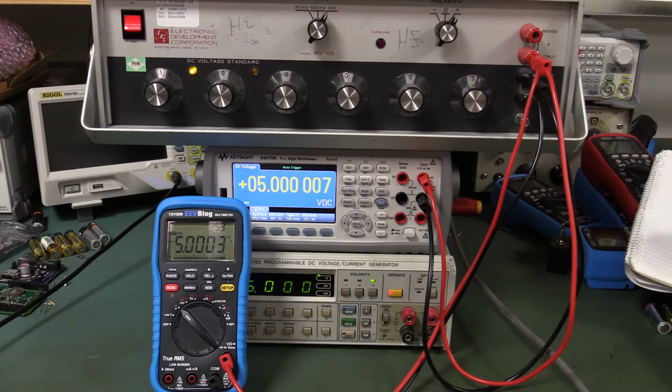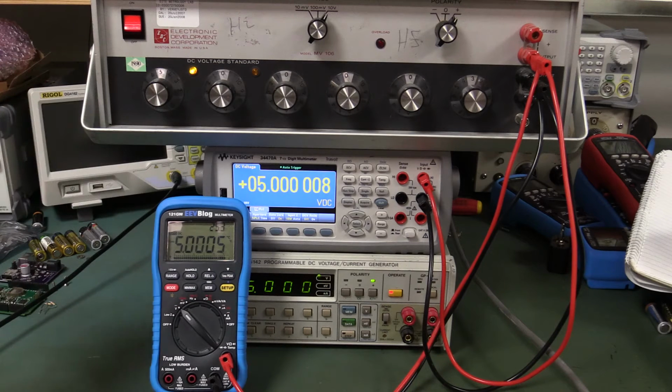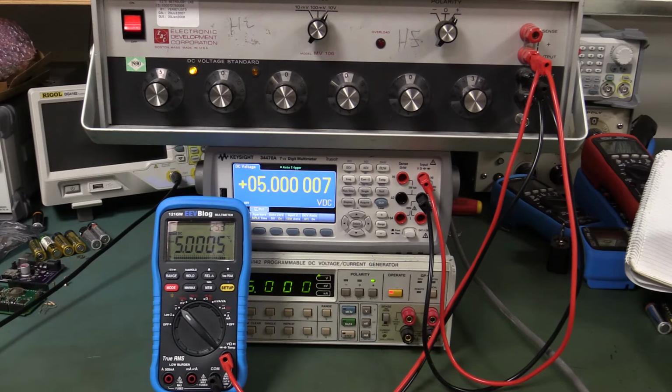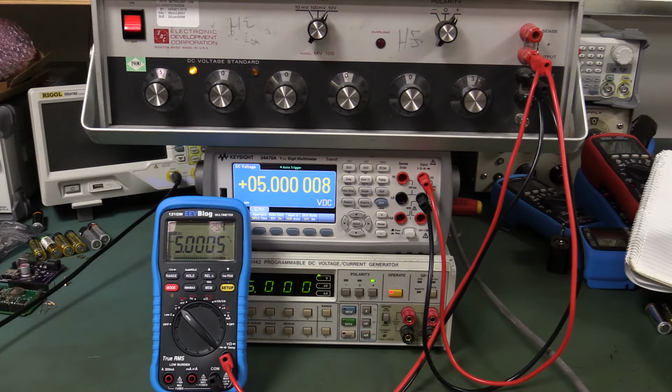I can see what you mean about noise potentially being an issue. So yeah, I'd like to see it with no noise filter at all, with no averaging filter at all on it. Because if you want averaging, you turn on the averaging mode in min-max av. So, you know, there should not be any averaging going on during normal operation. You can see that it's drifted by 5 least significant digits there, even though the value over here hasn't drifted at all. So yeah, it's a bit of a concern. We need to fix this one up.